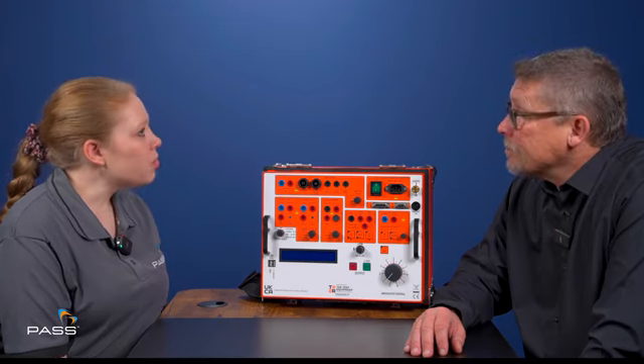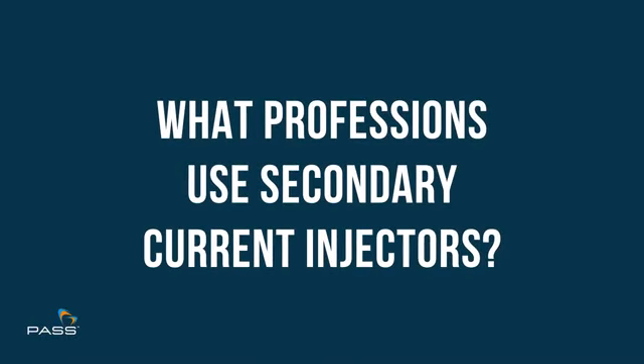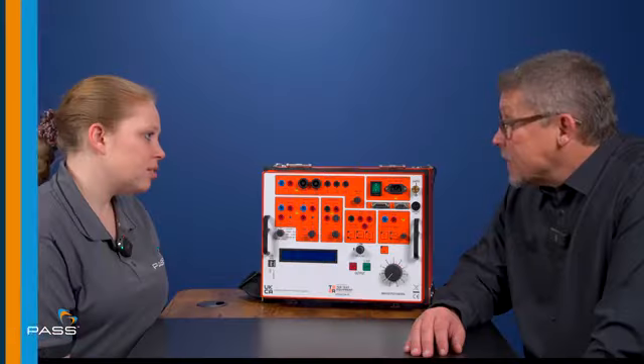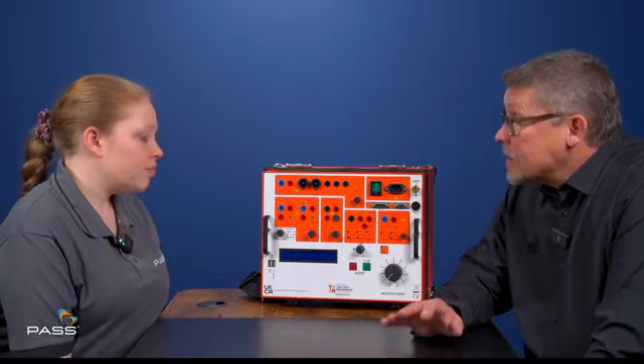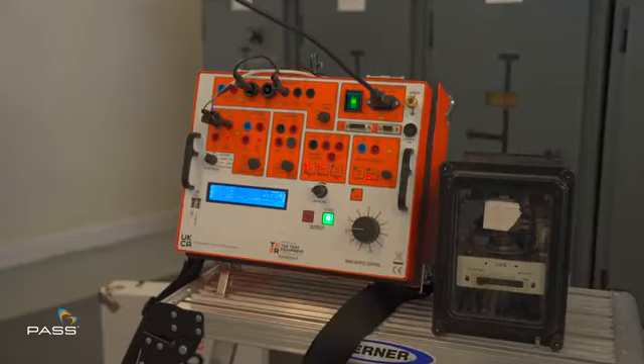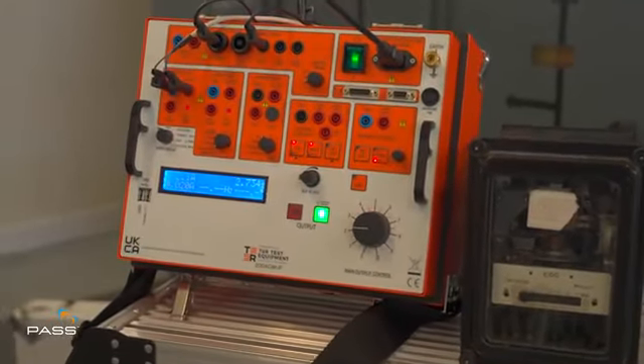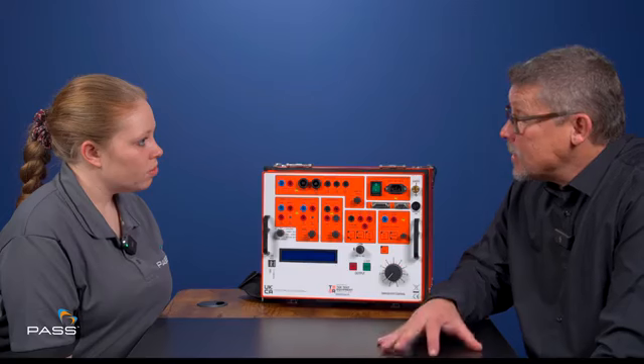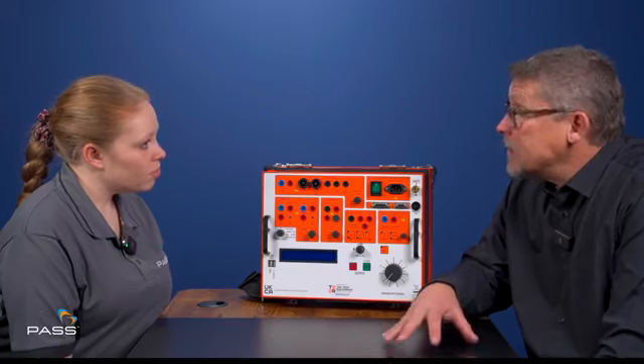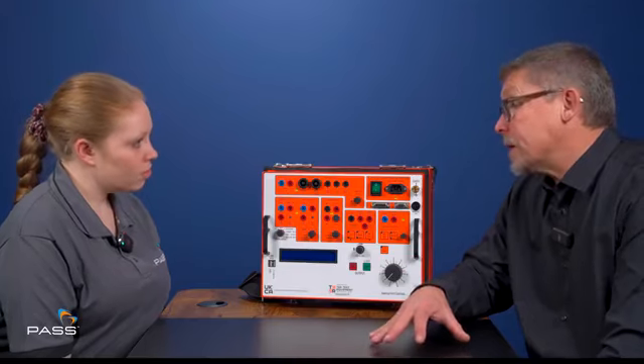And what sort of professions use secondary current injection testers? Majority of these will be used by commissioning engineers and testing technicians. So the commissioning engineers, when they commission a substation, switchgear, particularly the relays within that substation, but they may use it also to put extended current into circuits to test those circuits for joints. And obviously then and thereafter, the technicians in a company will use the unit to regularly test the relays that are in the circuits.